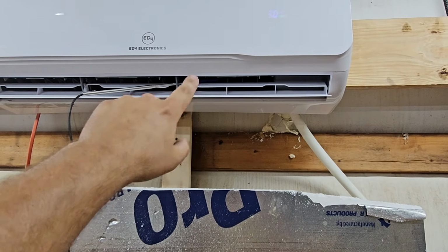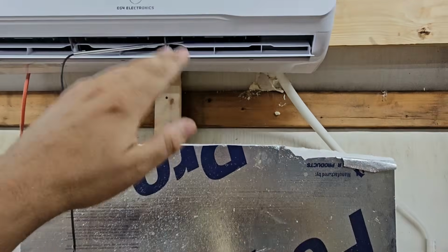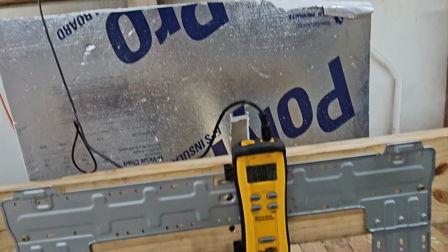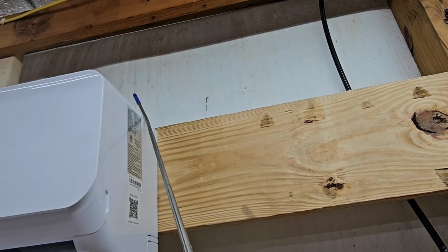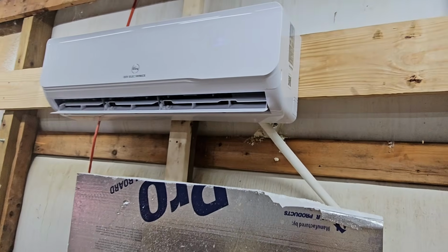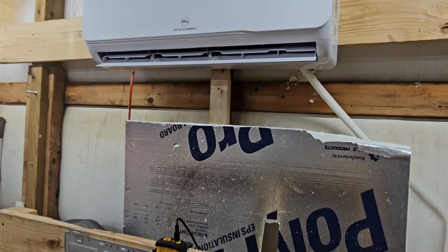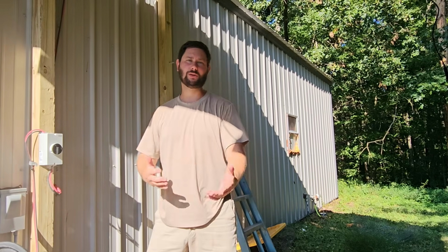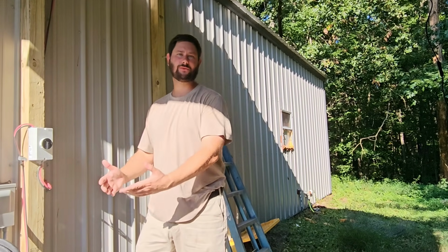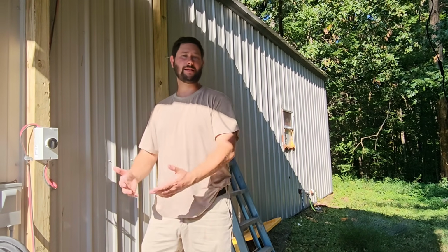So let's check out the exact return air temperature, and then we'll know what our split is. Measuring our return air temperature, 74. Nice. So we got exactly a 20-degree split. That's perfect. Factory charging a mini split is the best way to charge a mini split. You weigh out what you recover, and then you factory charge the equipment with what it's rated to hold. That's the best way to charge it.